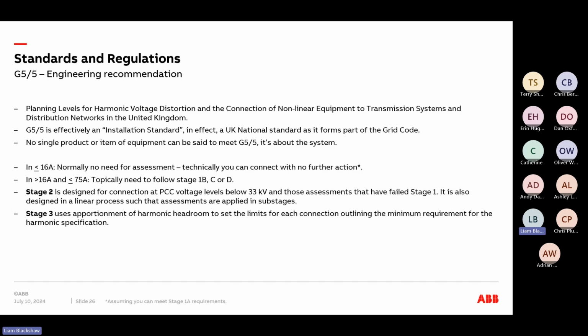Stages 2 and 3 are designed more for connections where the point of common coupling, so where you're measuring, is at levels below 33 kilovolts, or when you've gone through the criteria and you're unable to adhere to stage 1, so you move on to stage 2. This process is now designed as a linear process, such that the assessments are applied in sub-stages, and the final one, stage 3, uses apportionment of harmonic headroom to set the limits for each connection, outlining the minimum requirements for the harmonic specification at least.